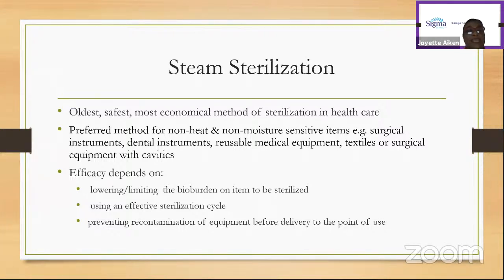Another point about the efficacy of steam sterilization, it depends on using an effective sterilization cycle. Remember in the slide just before this, we spoke about the density of the packaging. So you have to ensure that the cycle that you are running is effective. You're not going for too short a period, because if you have a full autoclave, then you have to make sure that you run for the appropriate period of time. It would be significantly less if you're just sterilizing a singular tray of instruments or a singular instrument.